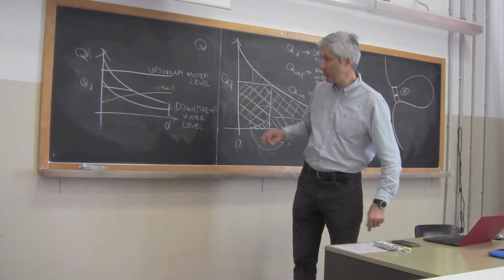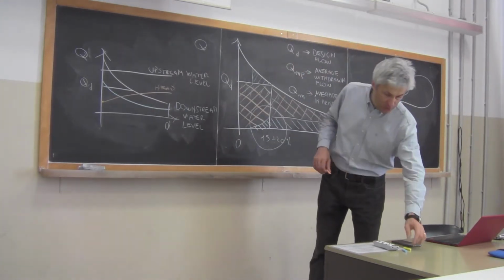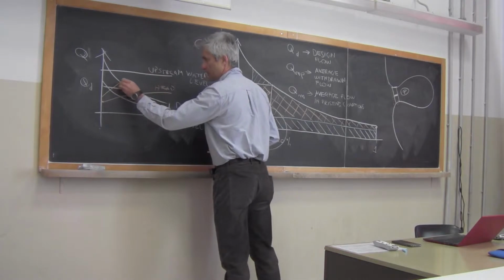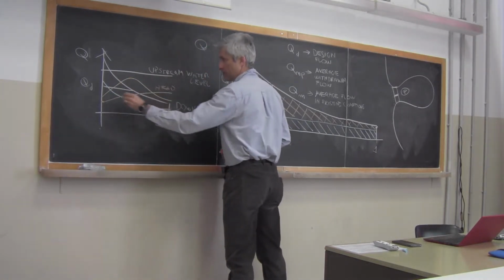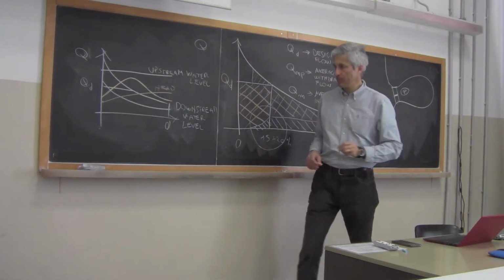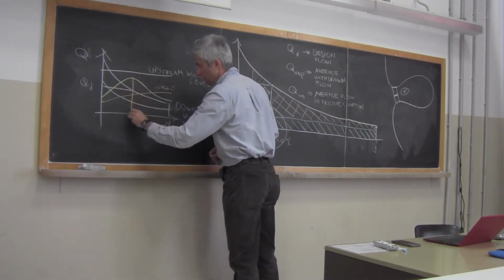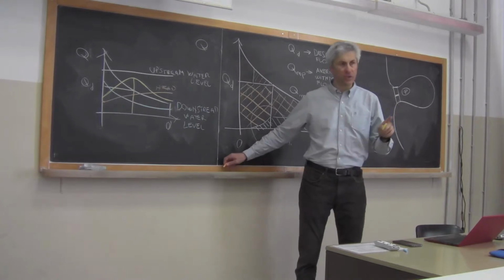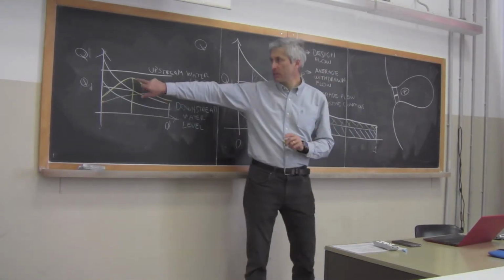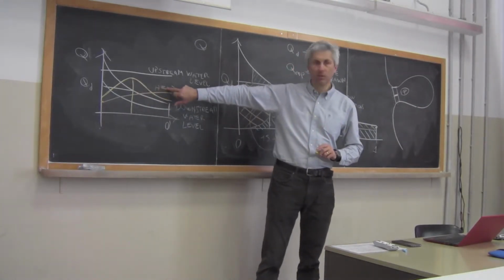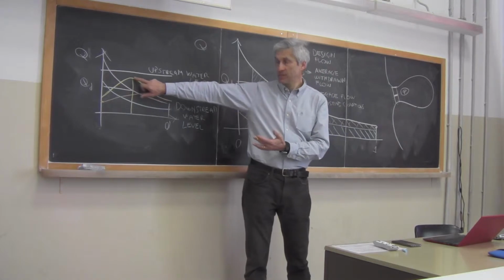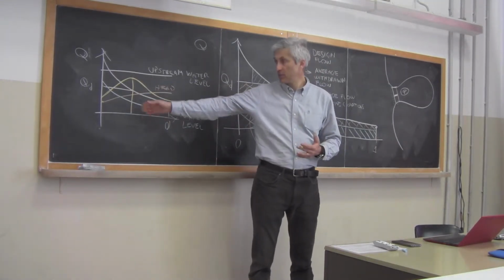So what is shown in the figure is also an energy production curve which looks something like this, with a max here. I think this figure that you find on my webpage is interesting, so have a look at it. Keep in mind that the max is not necessarily located here, because the increase in head could compensate the decrease in flow, but this doesn't happen in this plant. So indeed we have the max here, the max at the duration of the design flow.